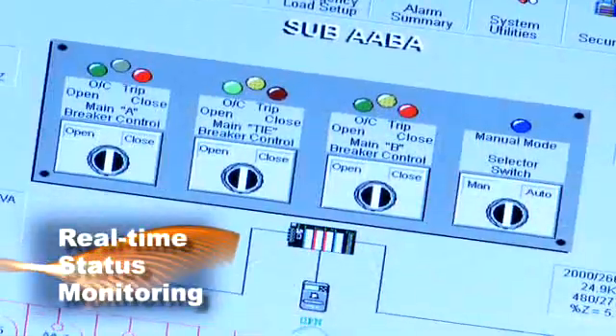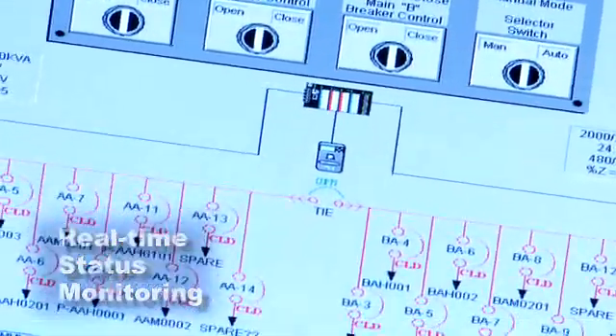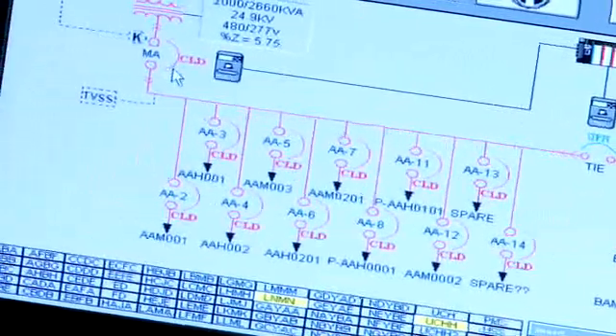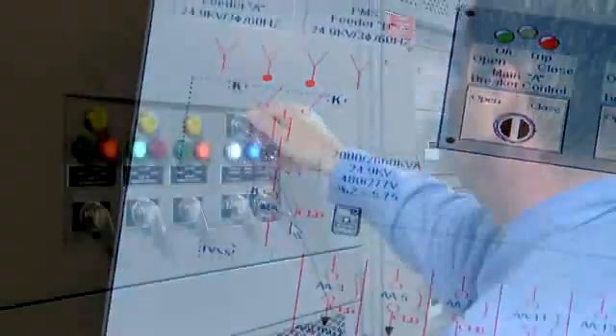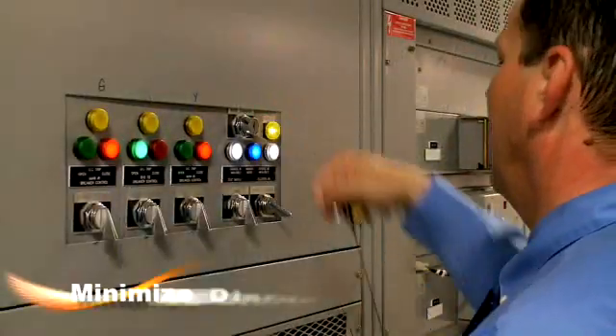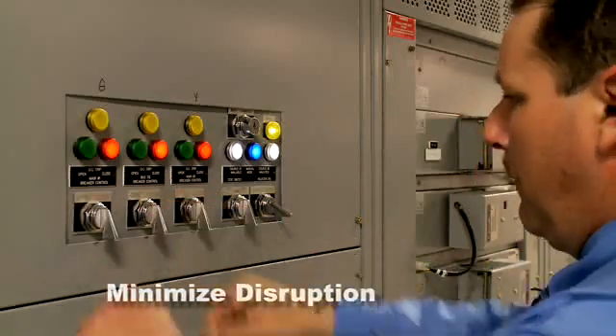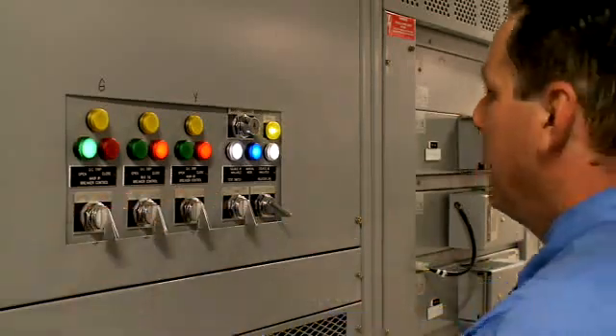Probably the greatest benefit that Wonderware has provided the Venetian in this power management system is real-time status monitoring. Data is used to look at power usage, but status monitoring—being able to tell the position of every breaker, faults, and alarms—allows the facility staff to respond at a moment's notice and helps them minimize disruption, which has the biggest effect on the Venetian's bottom line. So with them being able to minimize that disruption, it has had a huge benefit for this facility.